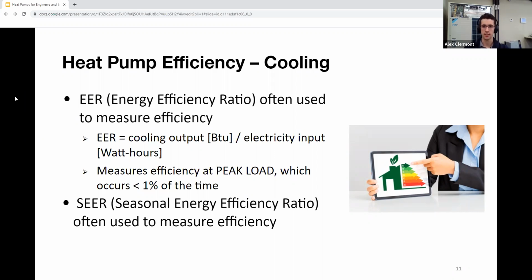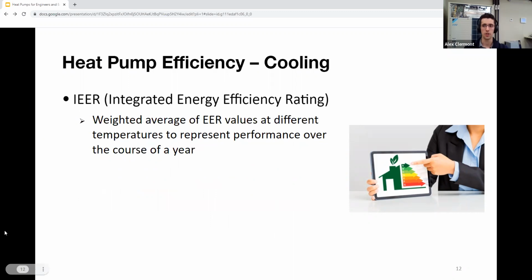SEER is also a metric that's often used, and that's the seasonal energy efficiency ratio, which is an efficiency metric that looks at EER over a range of conditions. Now, unfortunately, there's no climate-specific SEER. You have the same SEER rating for a unit in Texas and in New England, so it's not the best representation of specific operation in every climate, but it does exist. Now there's also IEER, which is the integrated energy efficiency ratio, which does look at different load profiles at different testing conditions to try to estimate the part load efficiency of the system. Now IEER is much better, but it's not perfect, and AHRI 1230, which we'll talk about in a little bit, is planning to make changes to how IEER is tested.